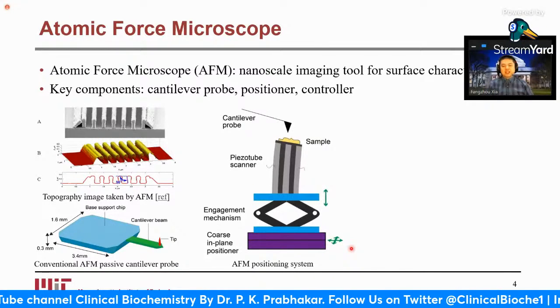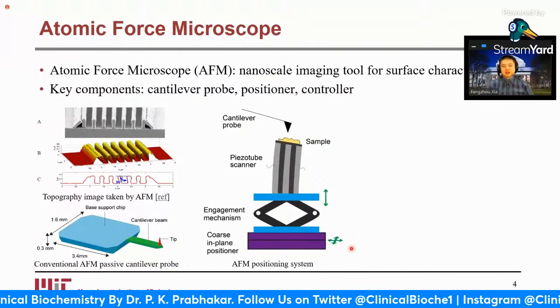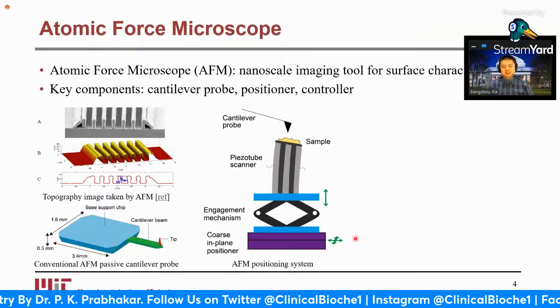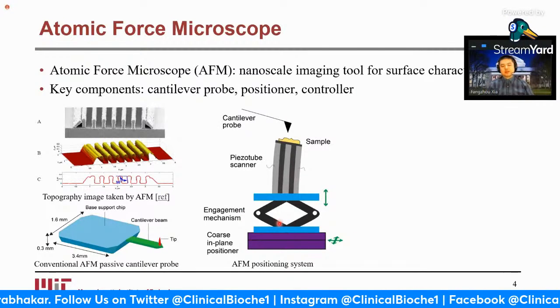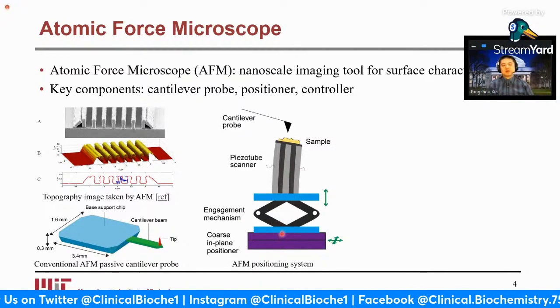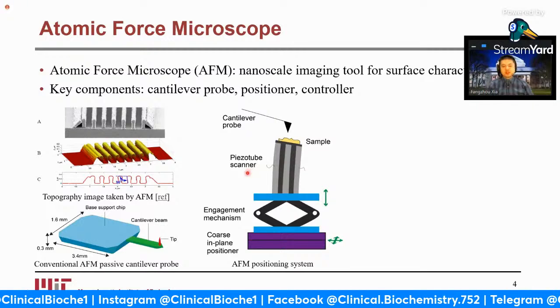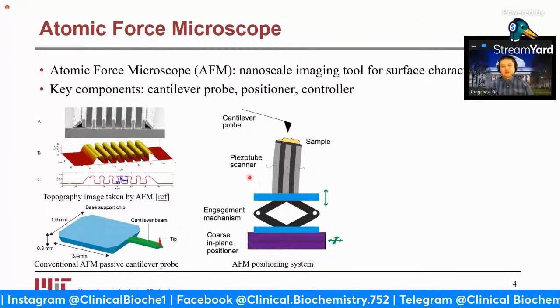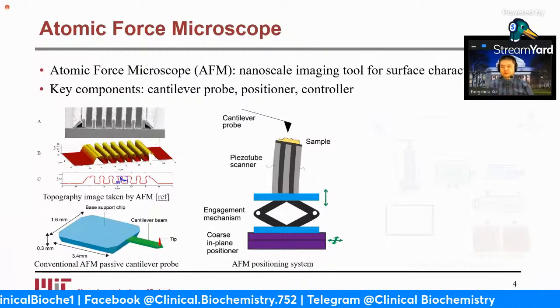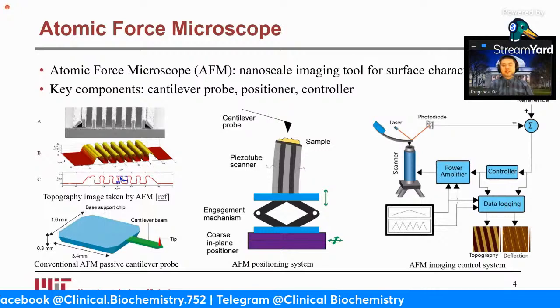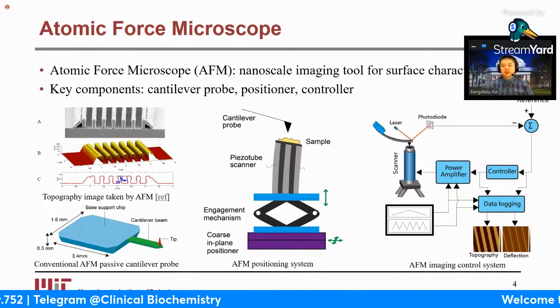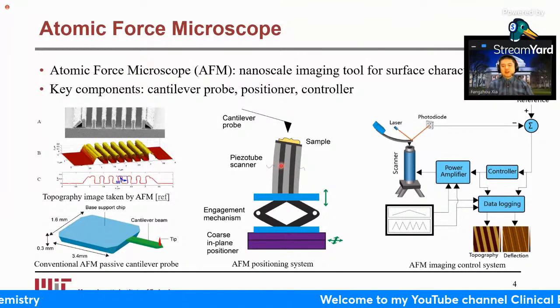This is the centerpiece of the AFM, which people utilize to interact with the sample. For the interaction, usually on the nanoscale, we need a positioner, which includes some engagement mechanism. That's the coarse motion to bring sample and tip into contact, as well as the fine piezo tube, or usually some piezo-based scanner, for motion control. Speaking of motion control, obviously we need some advanced stabilization system to implement the controller so that we can regulate the motion of the piezo scanner and then generate the desired image.